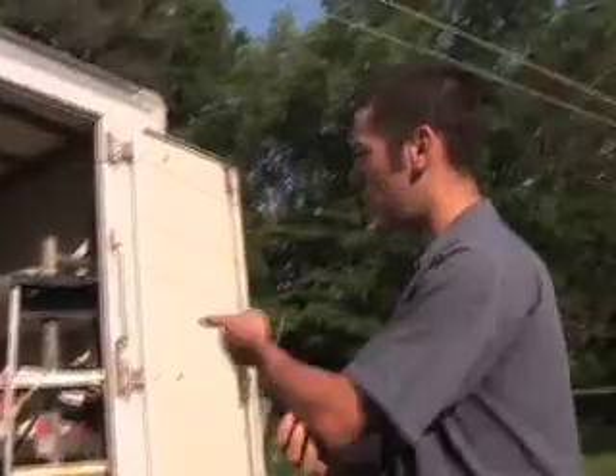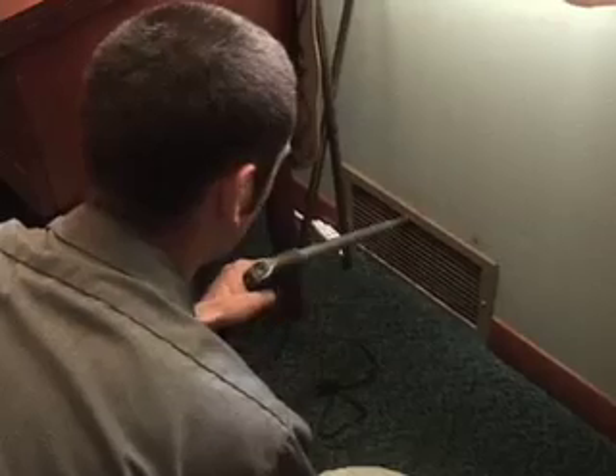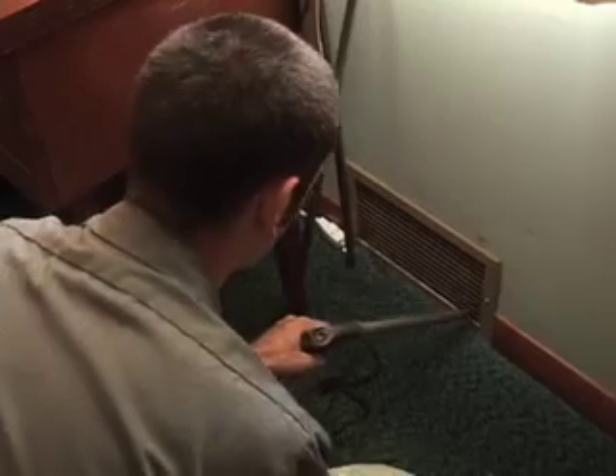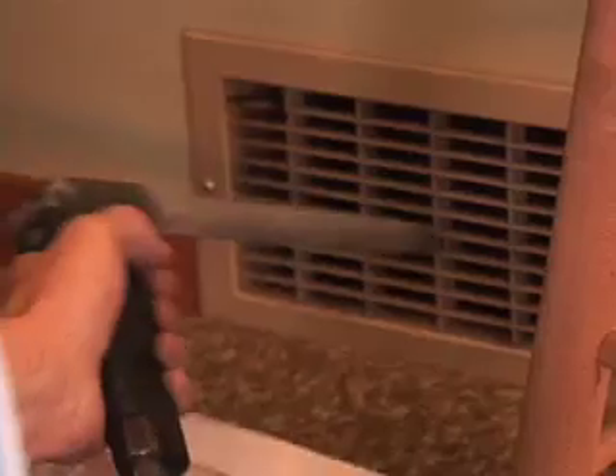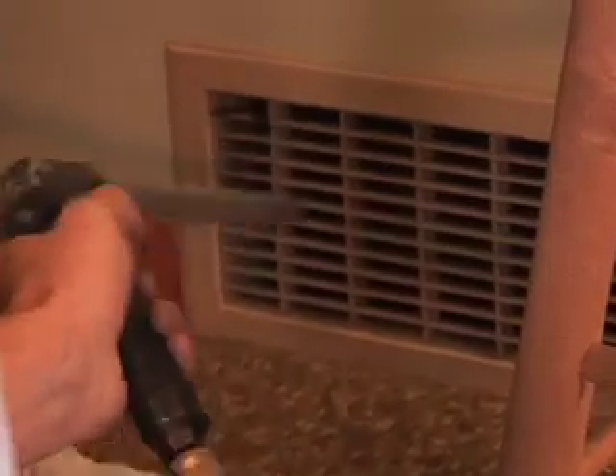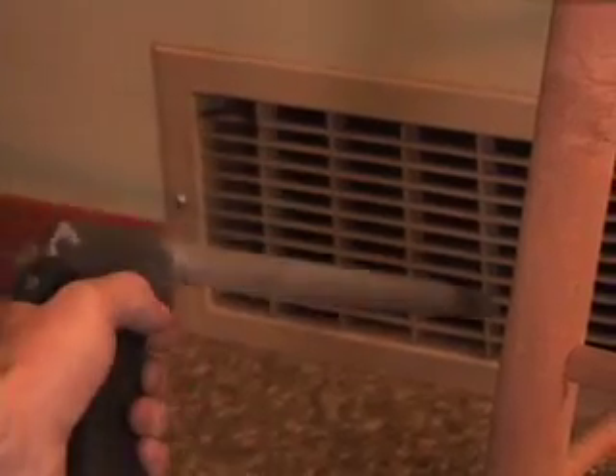I'm gonna just pull out my air compressor. That gives us 200 psi. We go around each register. We have suction on the register, so that's pulling everything back. We're gonna hit the registers with the air gun, and that's just gonna send everything right down into the ductwork to clean out all the boots and everything. What this does is agitates the debris inside the ductwork, and the vacuum cleaner, being a 2,500 cubic feet per minute vacuum cleaner, is going to pull all the contaminants back to its source. Usually if you hit this and you didn't have a vacuum, you'd have dirt everywhere. But with that vacuum going, you hit it with the air, it loosens it up, and it just instantly pulls it right back down into the vacuum.